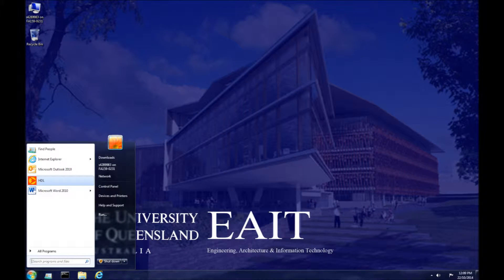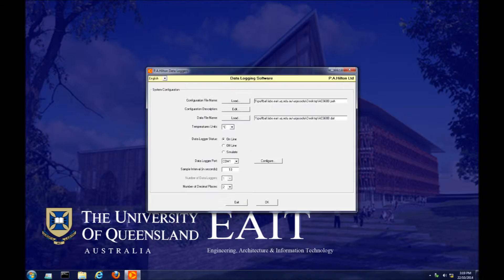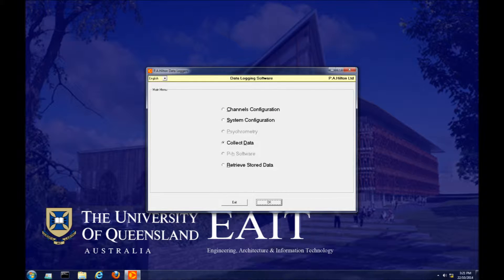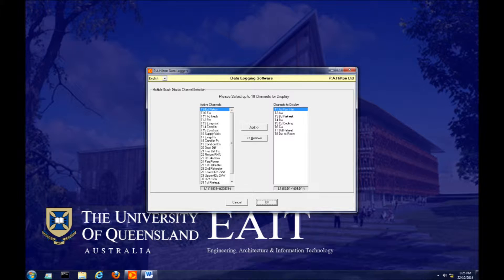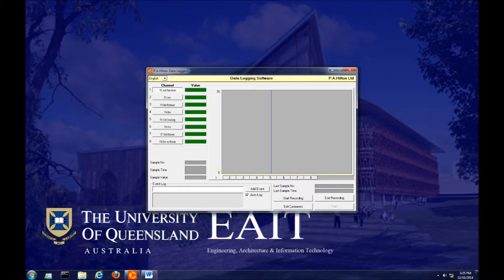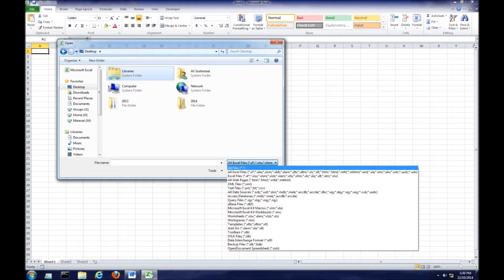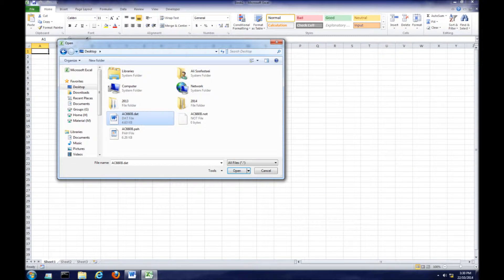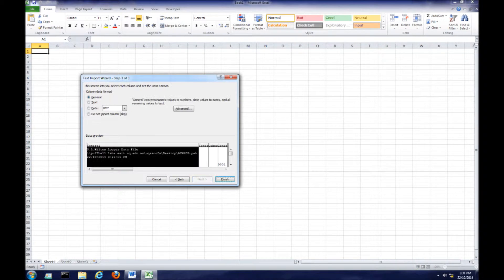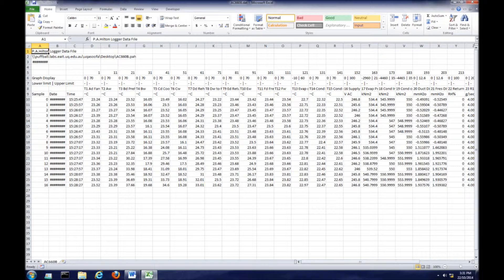You must now set up the computer program for collecting data in the duct. Open HDL as shown and select the language as English. The data file name needs to be selected as test 1 and the sample interval needs to be 10 seconds. You can now collect data and select the multi-graph display option. You want to view the data from sensors T1 to T8, then press the record data button and wait 30 seconds to allow the program to begin recording data. Once all the data has been recorded you must end the recording and exit HDL, then open the file in Excel. To find the file you must change the file type to all files and then open the DAT file. You will then be given a series of prompts — to open the file correctly you must select delimited, semicolon and then general from the options. The Excel file you now have can be saved and sent to all prac participants.